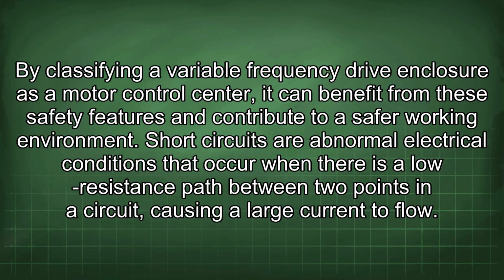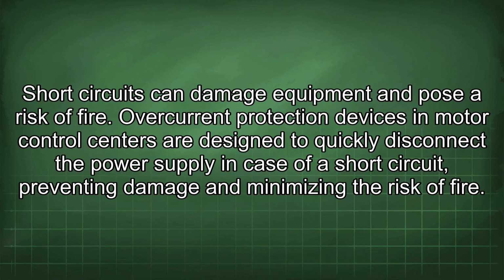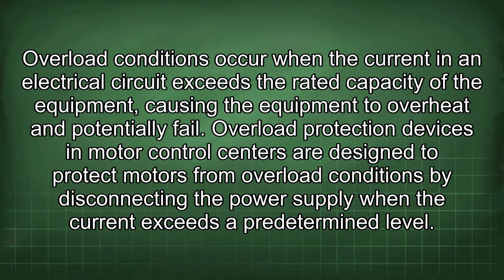Short circuits are abnormal electrical conditions that occur when there is a low resistance path between 2 points in a circuit, causing a large current to flow. Short circuits can damage equipment and pose a risk of fire. Overcurrent protection devices in motor control centers are designed to quickly disconnect the power supply in case of a short circuit, preventing damage and minimizing the risk of fire. Overload conditions occur when the current in an electrical circuit exceeds the rated capacity of the equipment, causing the equipment to overheat and potentially fail. Overload protection devices in motor control centers are designed to protect motors from overload conditions by disconnecting the power supply when the current exceeds a determined level.